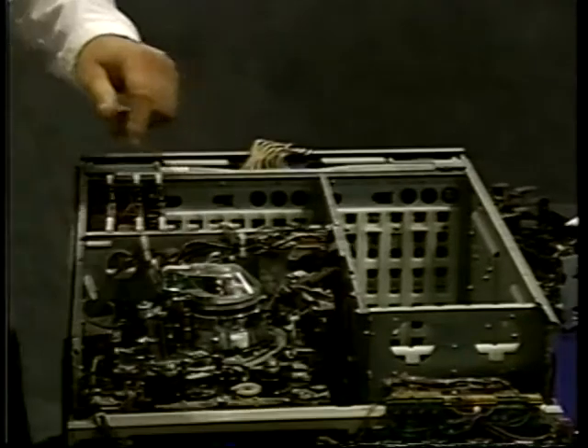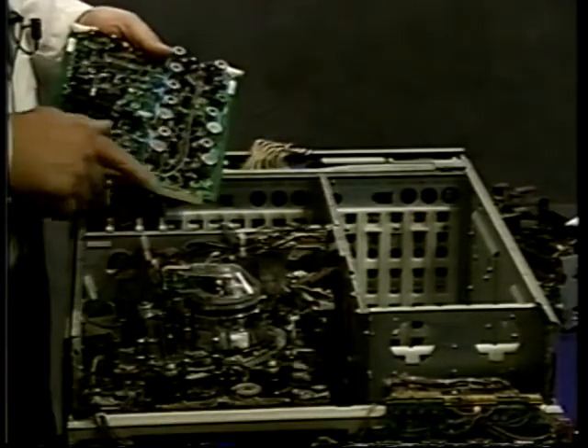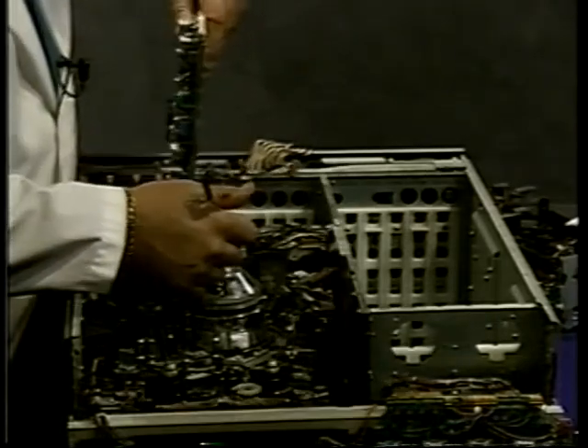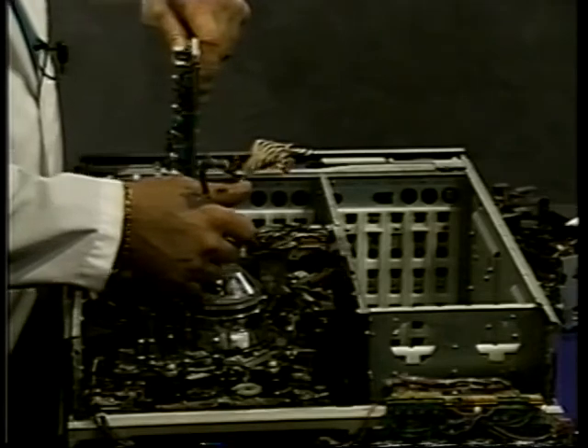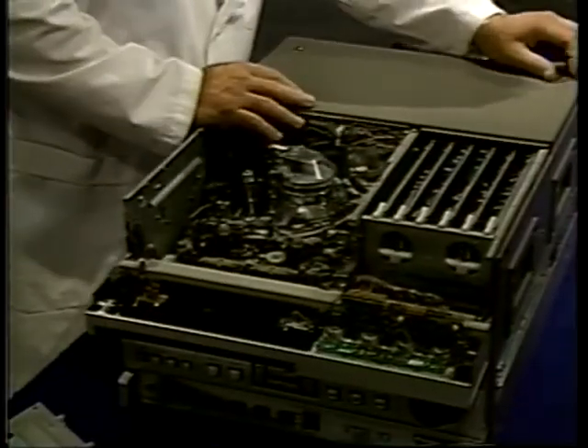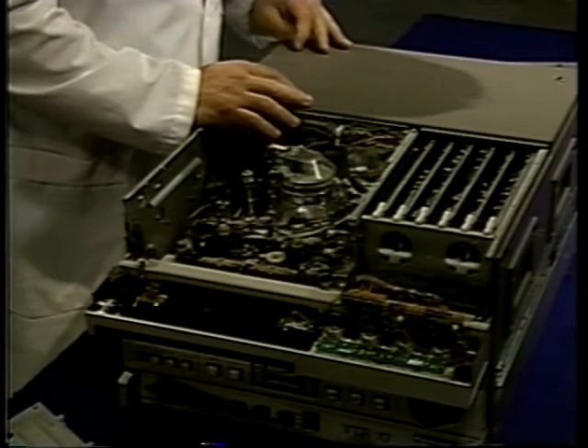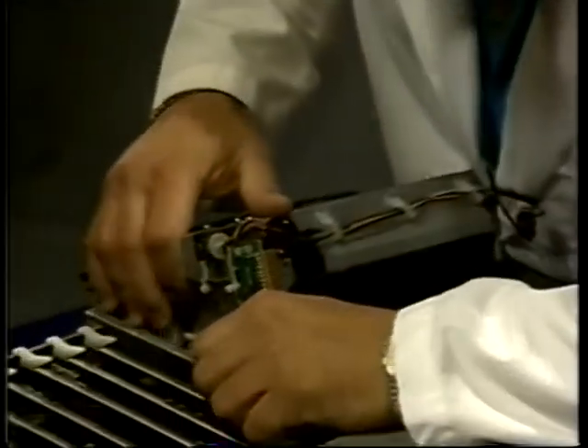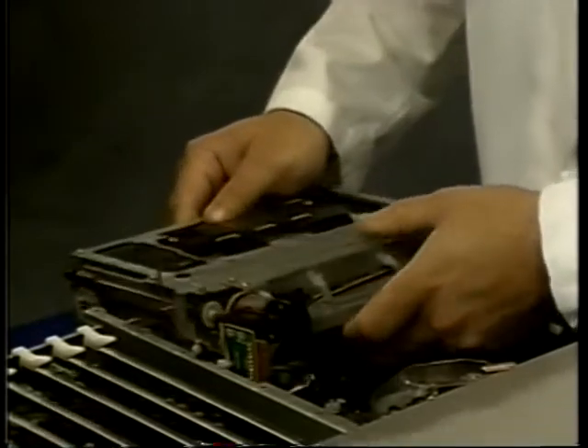Now replace the boards. Make sure all the edges are clean before they are replaced. Reconnect any of the connectors as you replace the boards. Replace the rear cover and tighten the screws. Now the cassette assembly can be replaced.